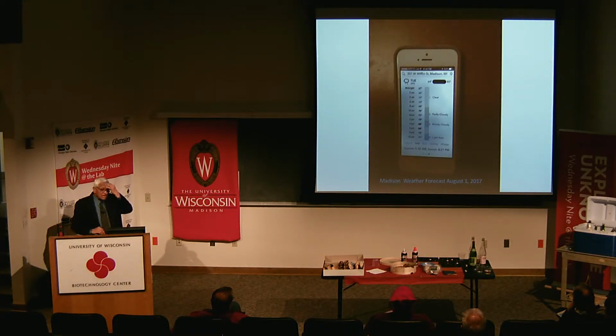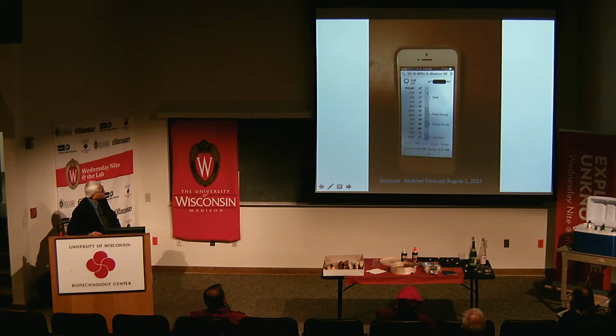Now here I have a weather app on my smartphone, and this is a 24-hour forecasted weather for August 1st for Madison. This is from midnight to midnight. As you can see here, you make ice. Because this is off-peak time, the rates are low, and if you've got an air-cooled centrifugal chiller, it's a function of outdoor air temperature. The cooler the temperature, the more efficient is the centrifugal chiller. So you make ice here, then around 5 o'clock or so, you start the optimal start program based on the decision of the optimization.